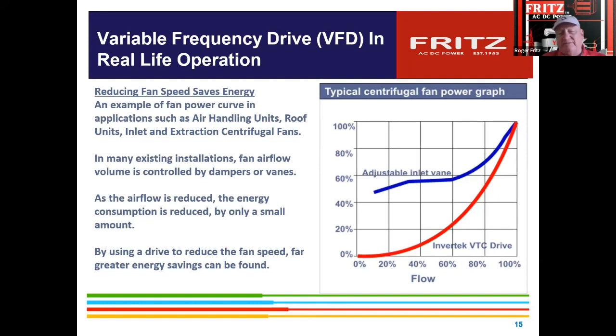why they found that VFDs on fans and pumps were their biggest hit at first was because you get the cube law. So if you slow a motor down 20%, the flow only drops 20%, but the actual horsepower drops by the cube factor. It's called the affinity law. So the motor is 0.8 times 0.8 times 0.8, it comes out to roughly a 50% horsepower reduction, not a 20-point horsepower reduction, similar to what you do when you put a vane or a valve on. You get that extra savings by the VFD. You do have a 1 or 2% loss in the VFD, because you don't get anything for free. It does have a few losses in it, but the overall efficiency is quite dramatic.